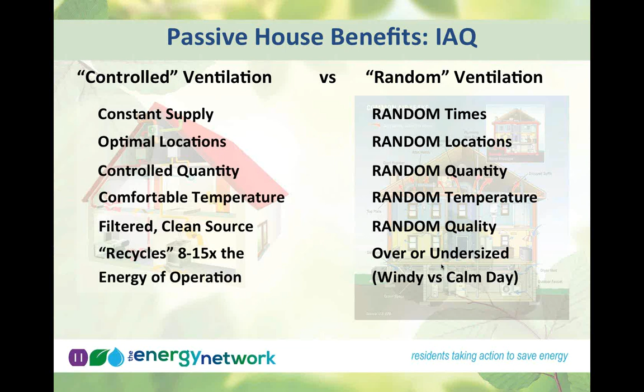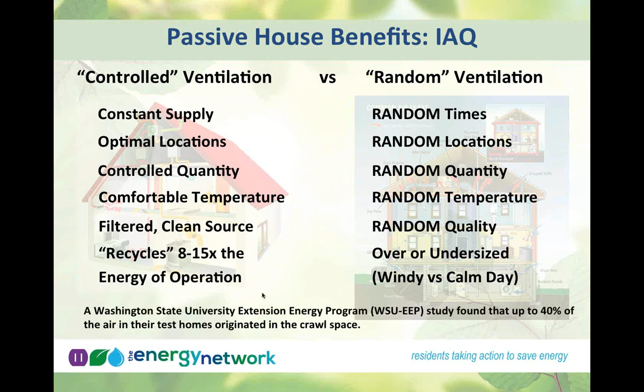Controlled ventilation, by contrast, gives you a constant supply from an optimal location, controlled quantity, comfortable temperature, and a filtered, clean source. In passive house, the heat recovery ventilation systems we use typically have very high heat recovery efficiency, on the order of 80 to 90%, and also very low electrical use. So even though these machines are running all the time, they recycle 8 to 15 times the amount of energy it takes to run them in terms of the heat they retain in the building.